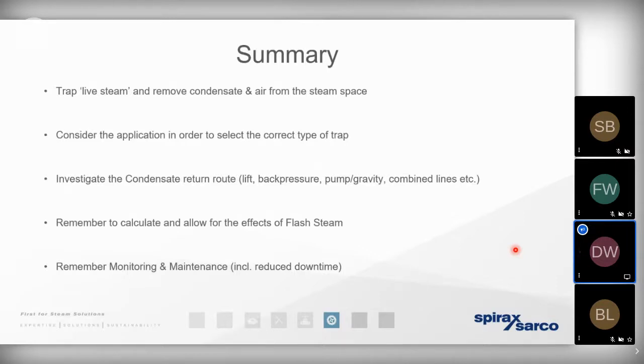But we know that any pressure drop of condensate passing across the trap is likely to result in flash steam. So just as it's important to size and select a steam trap correctly, it's important that we size the condensate pipework upstream and downstream of the trap correctly. One without the other is a waste of time. And we also want to ensure that we monitor and maintain the steam traps correctly, bearing in mind that they're not a fit and forget solution.